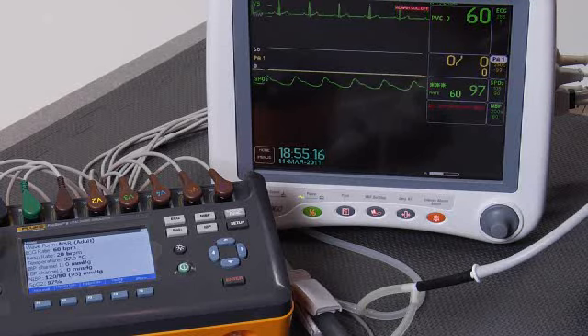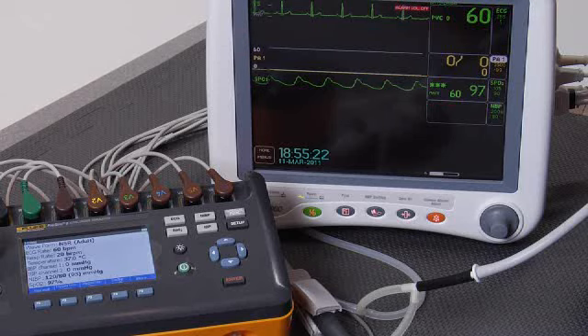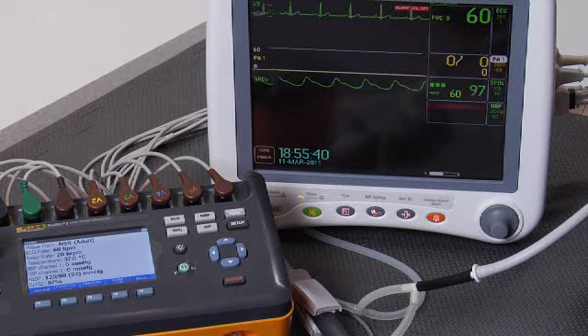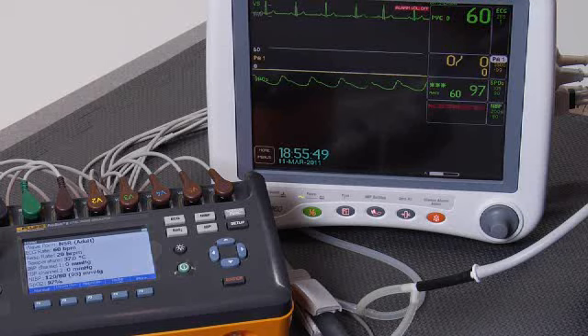There's a digital clock shown in the lower left-hand corner of the patient monitor display, so you can be your own judge as to whether we can get through this test within five minutes. As I begin the test, we are already connected to the device under test. All of the connections have been made ahead of time, including the NIBP cuff. We are going to zero our invasive blood pressure transducers on the patient monitor as the very first step, followed by a selection of a simulation of all coordinated patient parameters.